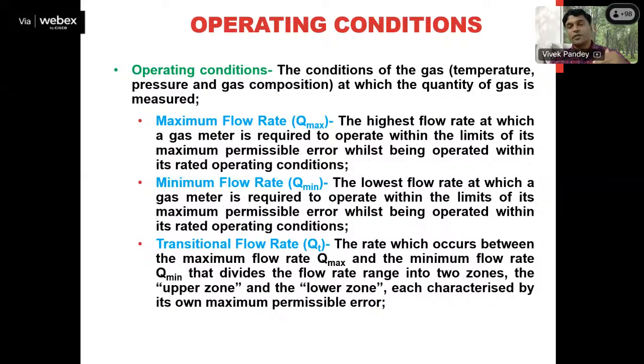So it means, for a particular gas meter, within the minimum and maximum flow rate, there is a prescribed tolerance in terms of its accuracy. That tolerance is different up to the transitional flow rate, and above the transitional flow rate the tolerance will be different, or changed. Suppose, taking the example of a particular gas meter, from the minimum flow rate to the transitional flow rate the tolerance will be something like 1%, and from the transitional flow rate to the maximum flow rate the tolerance of the gas meter with respect to its accuracy will be different, like 0.5%. This tolerance is changing, which means its accuracy is changing. Fine. So this transitional flow rate is also an important flow rate which is specified by the manufacturer.